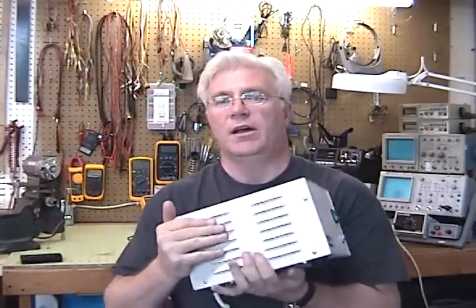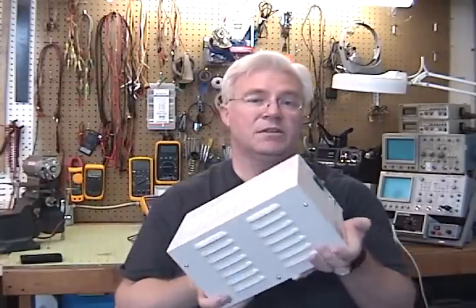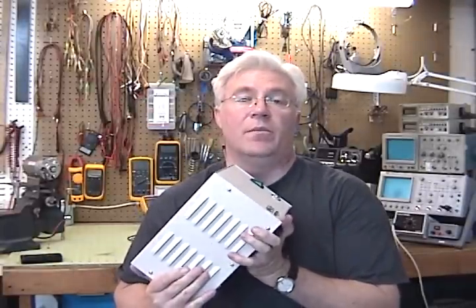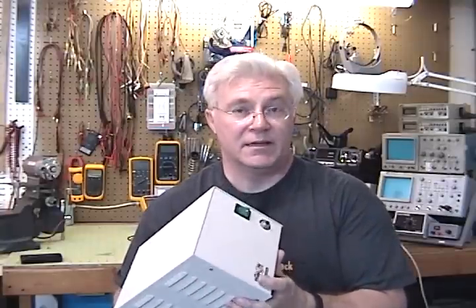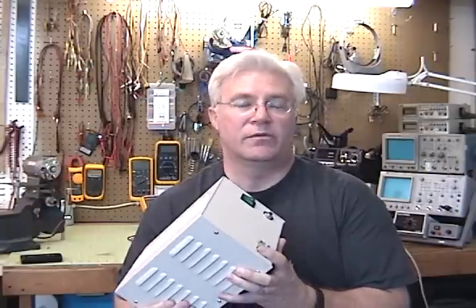But with an isolation transformer, the primary is on this side, the secondary is on this side, and the current will only flow through the secondary loop. Hence, if you touch any part of the secondary and your feet are on ground, ground is no longer a reference point to the secondary side of the transformer. So you can't be in the circuit, nor can your oscilloscope or any other piece of gear. For a tech bench, that's true. But when you buy one of these publicly available isolation transformers like a Tripp Lite, they actually tie the secondary coils to ground. They do that for common mode noise canceling for the sensitive equipment. That's no good for you as a technician, because now the secondary is also on the ground plane with everything else. So if you become a short between your circuit under test and any ground, you're still hurt, and so is your equipment.